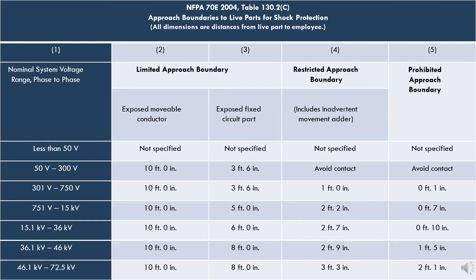Finally, the prohibited approach boundary. You should keep in mind that if you're within this area, you're basically working on it. Even though it says 7 inches from the exposed electrical circuitry, you're considered to be working on it. That's when you need insulated tools only, along with your dielectric protection and FR clothing on.